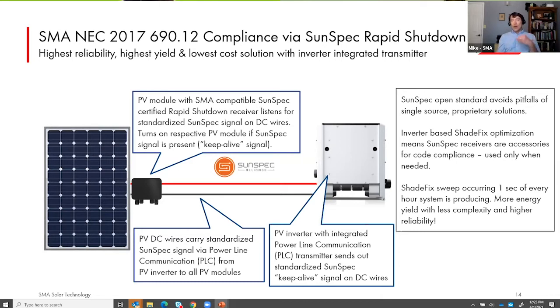The benefit of going with SunSpec as well is that this is an industry standard, an open standard. SMA is a part of the SunSpec Alliance, and the SunSpec Alliance published this open standard for power line communication signaling to comply with the rapid shutdown requirements. The transmitter built into each and every Core 1 has been certified by SunSpec to comply with that open standard, and it is responsible for putting the keep alive signal on the DC conductors going between the inverter and the array to send that keep alive signal to the rapid shutdown receivers at the array. And those devices, again, are only responsible for monitoring that that signal is present.